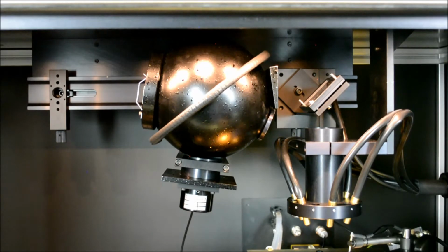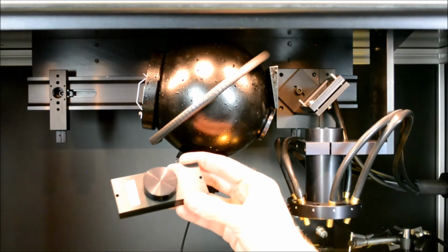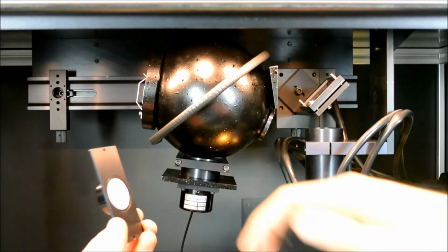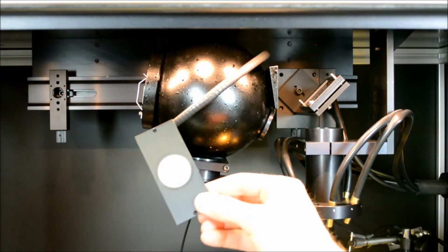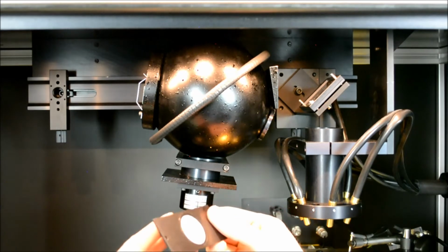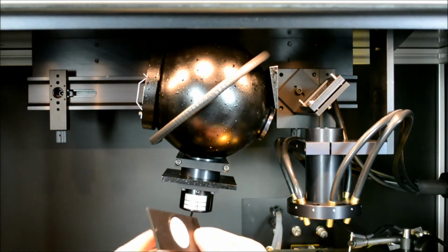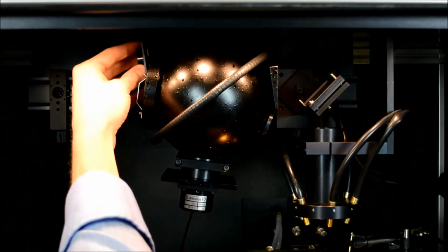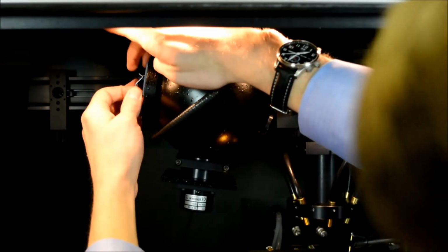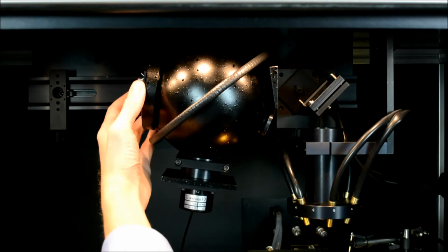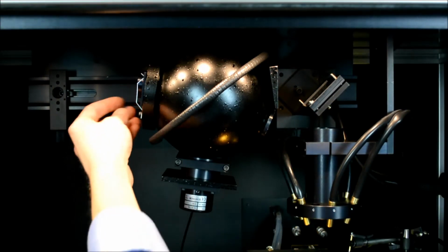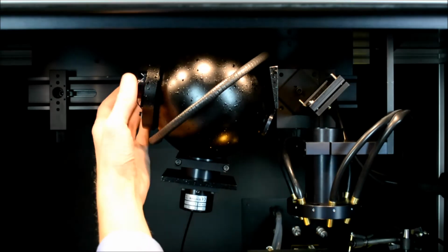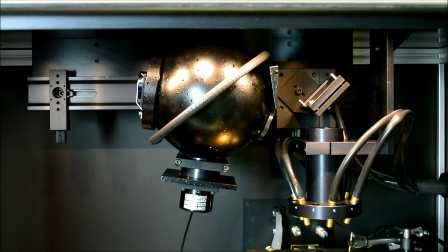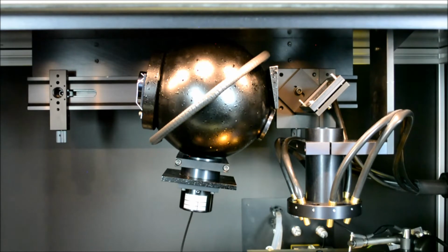To calibrate the system for the measurement of spectral reflectance, the system is accompanied with a DTR6 reflectance plaque. This plaque has been provided with a cover and has been provided with calibrated data over the range of use of the system. This plaque should be positioned at the reflectance port, held in place using clips, making sure that the reflectance port is entirely covered with the diffuse reflective white material.